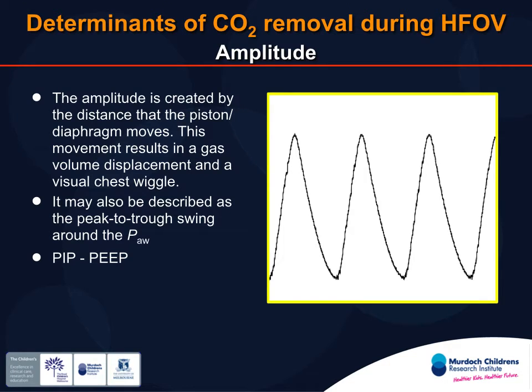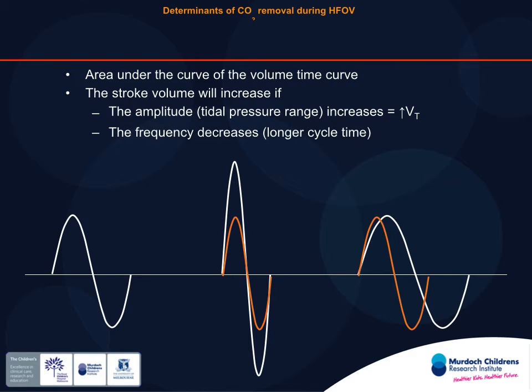So the amplitude is created by a piston or a diaphragm or a series of jets or some other thing which is moving or changing the flow and the pressure in the system. And this causes the gas volume displacement and causes the chest to wiggle. And it is essentially the difference between the peak and trough swing around your mean airway pressure. So it's equivalent to your high frequency PIP and your high frequency PEEP. The area under the curve of your high frequency waveform is the stroke volume. So this is your tidal volume, the area under this curve, okay?